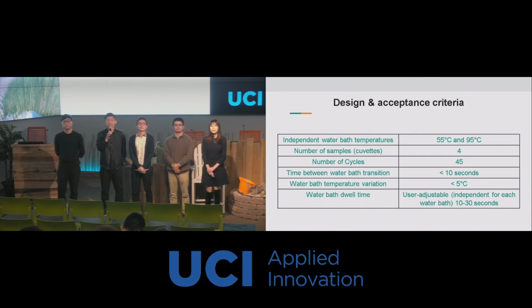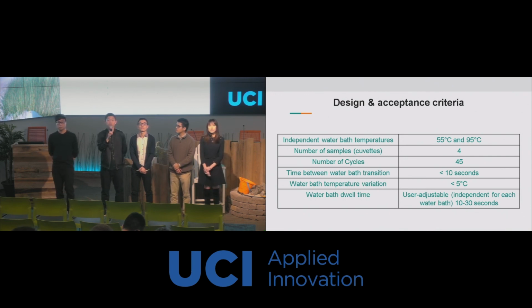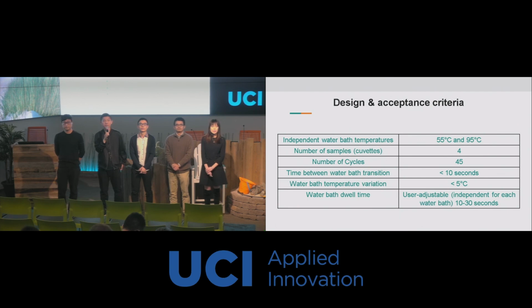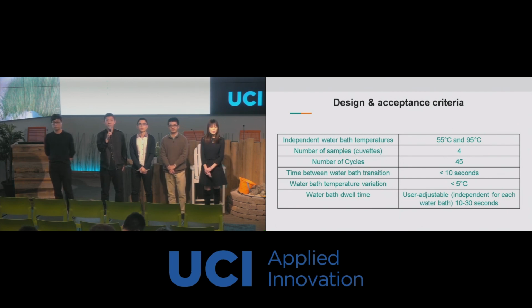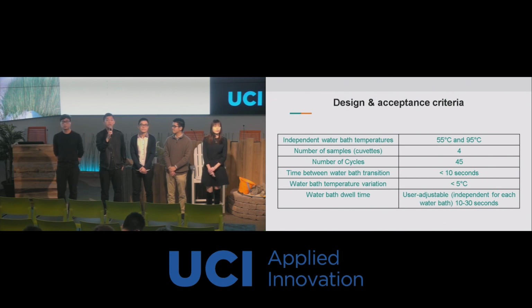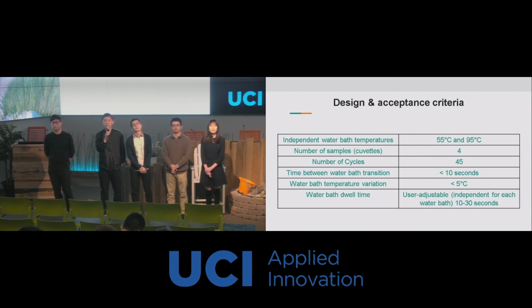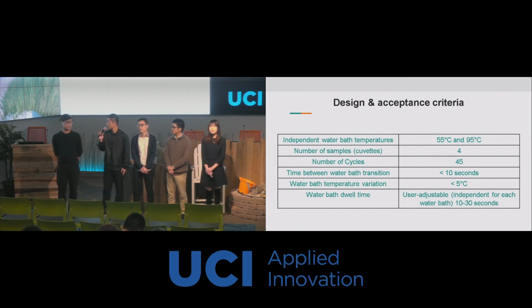So let's talk about the design criteria. First, we need two independent water baths, and the temperatures of the two water baths will be 55 and 95 degrees Celsius respectively. The number of sample cuvettes will be at least 4 for one operation, and the number of thermal cycles will be at least 45. The time for the water bath transition needs to be less than 10 seconds. The water bath temperature variation will be less than 5 degrees Celsius. And the water bath dwell time needs to be user adjustable and independent for each water bath, varying from 10 to 30 seconds.